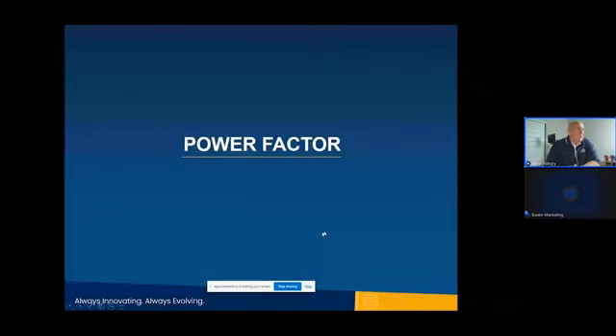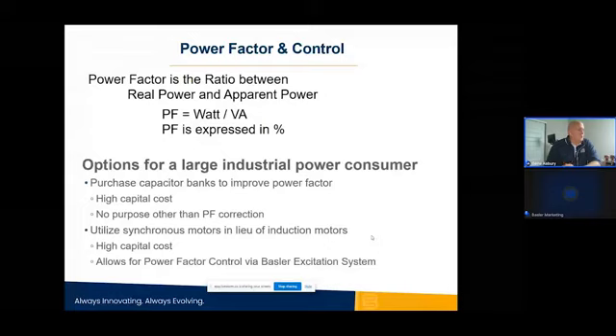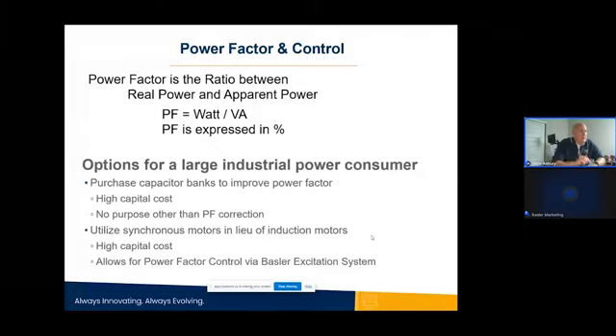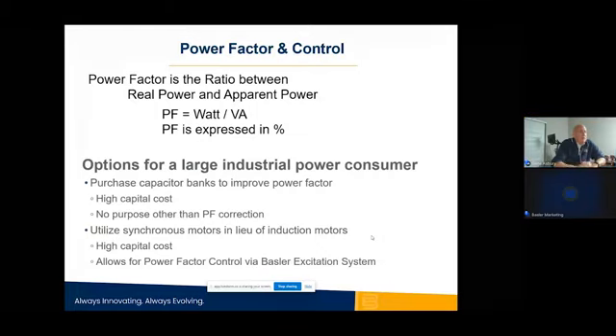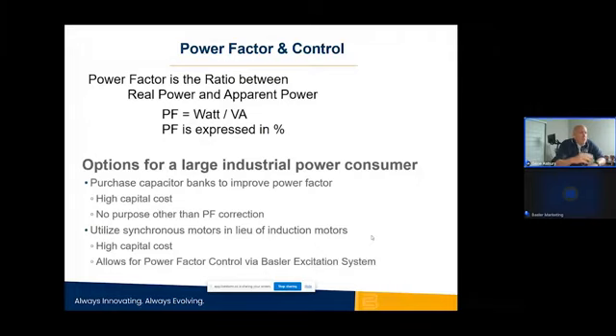So power factor is an important part about a motor. Power factor is a ratio between real power and apparent power. It's expressed in percentage. So as I said before, if we're regulating power factor, we're looking at the cosine of the angle between the real power and the reactive power. And that's where our set point target is, maintaining that power factor. And I should say, in most motors that have a constant load on them, we're going to regulate power factor. On some motors, like a chipper motor, where the load is always fluctuating, some people like to use the VAR mode of regulation, where it's looking at the VARs instead of the power factor. Either one works, but like I said, for a constant load and things like that, power factor works the best.